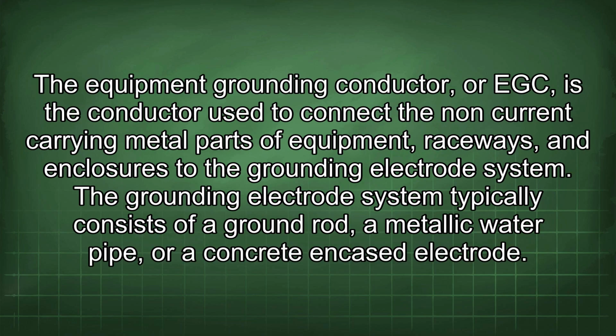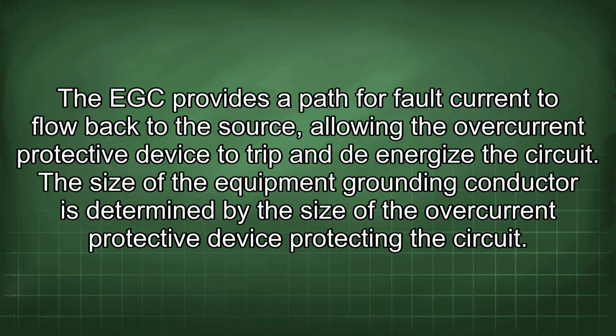The equipment grounding conductor, or EGC, is the conductor used to connect the non-current carrying metal parts of equipment, raceways, and enclosures to the grounding electrode system. The grounding electrode system typically consists of a ground rod, a metallic water pipe, or a concrete-encased electrode. The EGC provides a path for fault current to flow back to the source, allowing the overcurrent protective device to trip and de-energize the circuit.